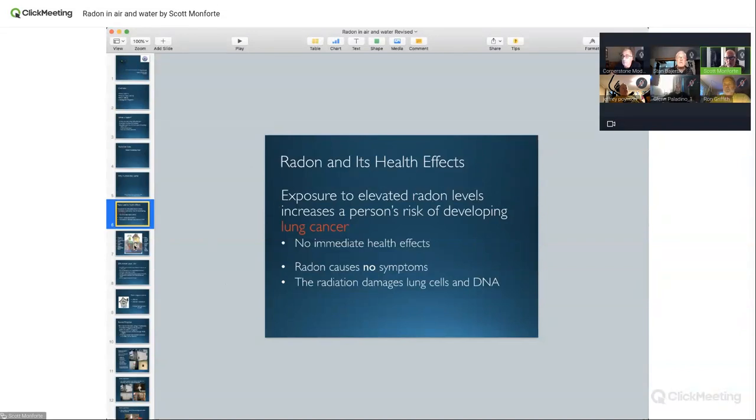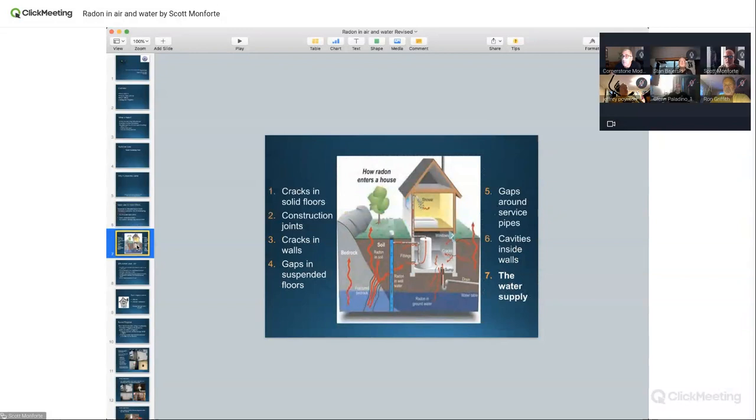So let's go here. We talked about how it damages the lungs. Now, cracks in the floor. As a radon mitigator, any cracks I see, not the hairline cracks, and sometimes you see those control joints that the builder puts in. Sometimes they just cut that with the K12, and if I stick a knife in there, it stops. It's just cutting along the top. Those I don't seal. If they go all the way through or they're cracked open, I'll seal it.